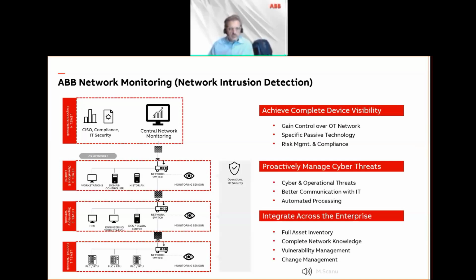the learning mode at the beginning. So you have to do a good baseline, otherwise you get some false positives. So it's important that you run the system and see which are the normal behaviors inside your system, so these are not creating false alarms.